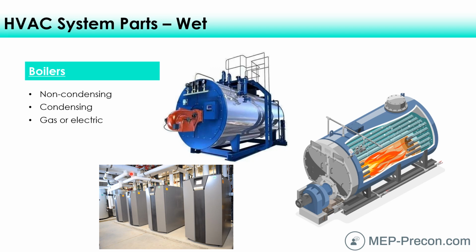And what do you suppose the efficiency of an electric boiler is? Well, electric boilers don't have a flue, so where else is the energy going to go that you put into it? You've got some elements, and surrounded around those elements is the water. So where else is that energy going to go? Yeah, pretty much all of that energy goes into heating the water. So electric boilers are pretty close to 100% efficient.